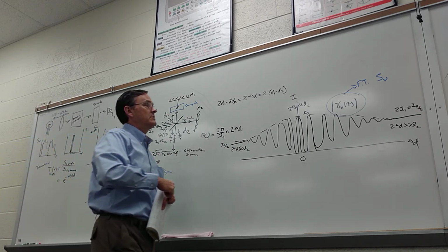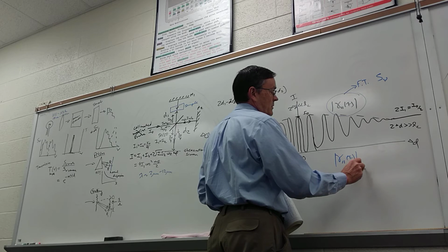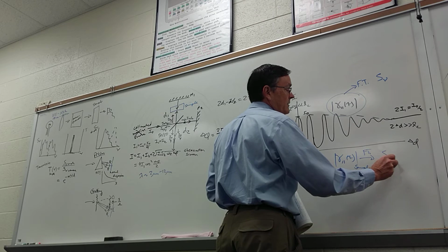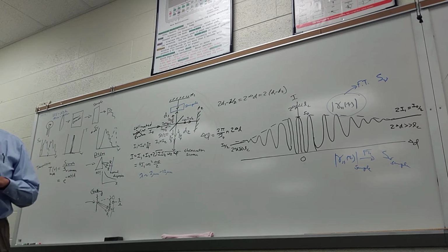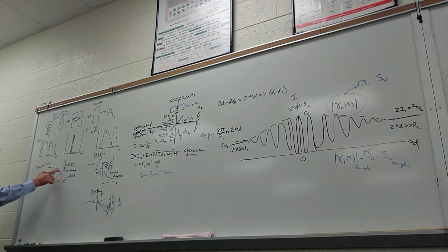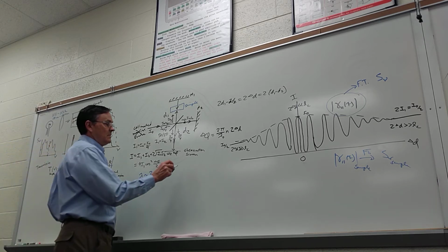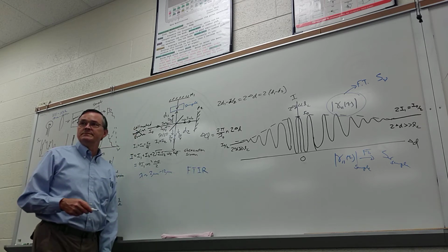So you measure that coherence for the sample, then Fourier transform again, and now you have the sample spectrum. And then it's just back to this, and you're at the same point. You've got the transmission for the sample, therefore you've got the absorption as a function of wavelength. And this is called a Fourier transform infrared spectrometer, an FTIR.